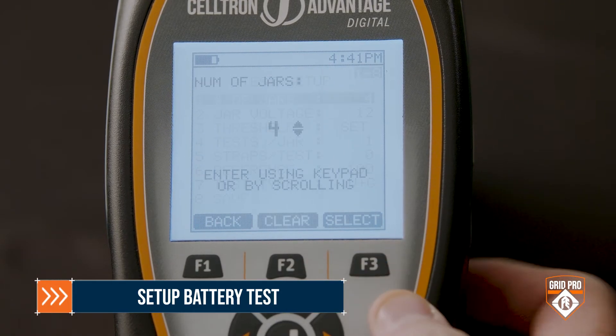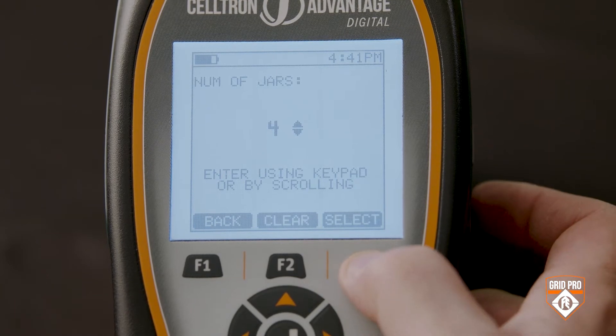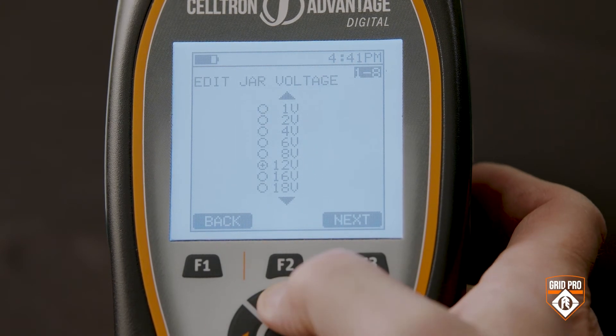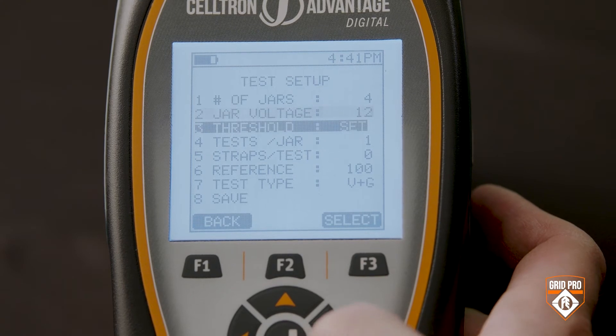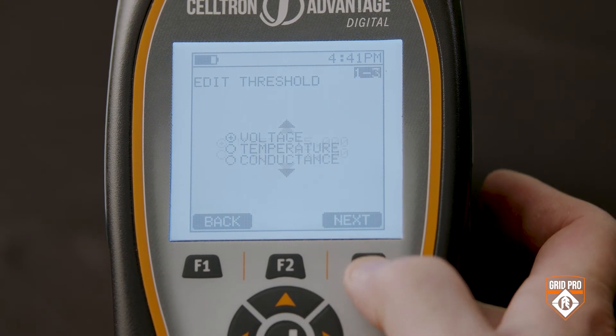Now you're ready to set up the battery test. First, enter the number of batteries or jars — the default is 4. Next, choose the nominal voltage for the batteries or cells you are testing. Then you're going to set the thresholds for the alarms for voltage, temperature, and conductance. You can choose the defaults or edit the default values.